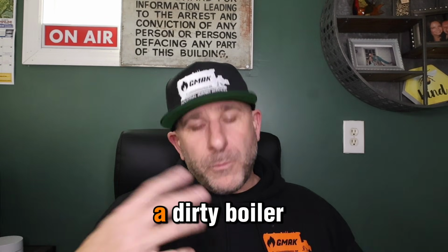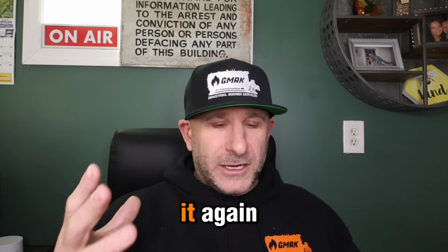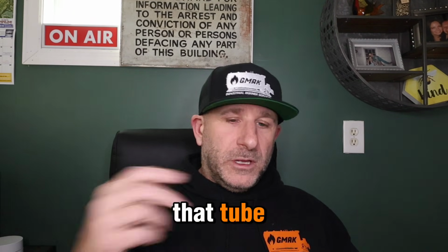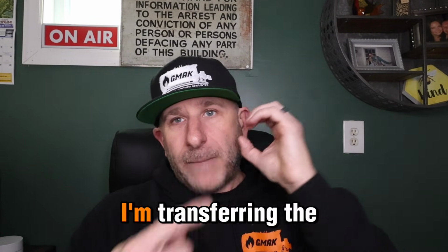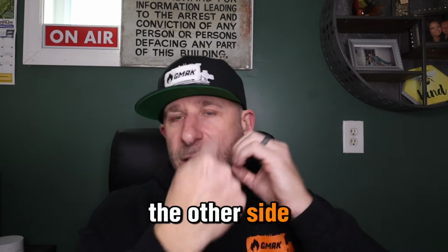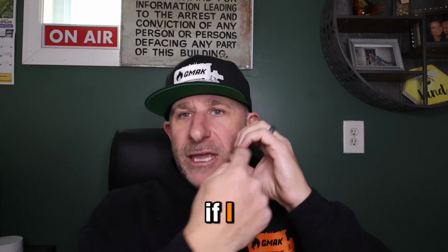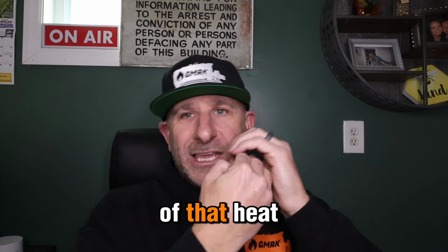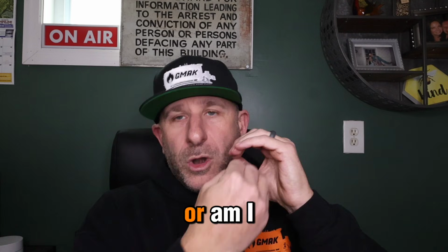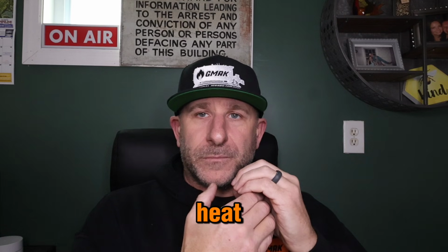Now, where a dirty boiler gets involved, if you're watching this, I've done this video before, but I'll talk about it again, is soot will build up on that tube. So if you think of anything else as you're transferring heat from one thing to another, initially I'm transferring the heat passing through this tube right straight to the metal, and right on the other side of this piece of metal, which is like a 10 gauge tube, is water, and I'm able to heat it. Now, if I insulate the inside of this hole and I pass heat through, does the transfer of that heat go through without any issue?